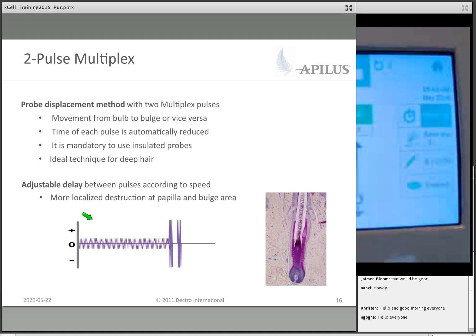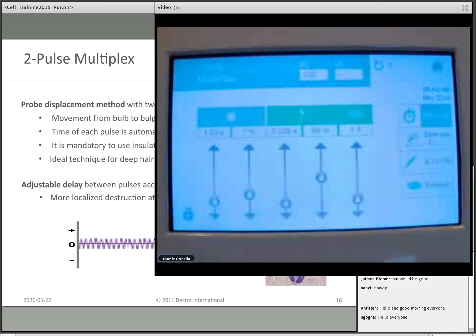I'm best to put it on the machine because if I use my foot, then what I'm doing is the pre-warming pulse, which is just going to waste time. So set your machine to 2 pulses. The machine will only do the pre-warming once, and it will deliver both pulses of high frequency Picoflash. Remember that you can still adjust the timing in between these pulses. So let's go and see what that looks like. Back to our video. First, I'm going to do 2 pulses without setting it. So as if I'm doing in the same insertion, 2 pulses of multiplex.